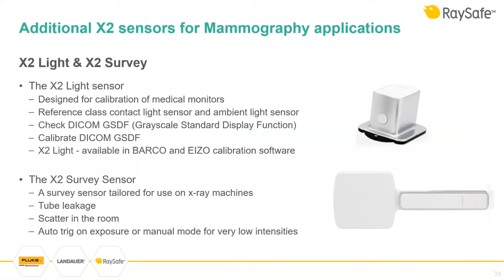Additional X2 sensors for mammography applications: the X2 Light sensor is designed for calibration of medical monitors — it's a reference-class contact light sensor with the capability to measure ambient light. You can use it to check or calibrate the grayscale standard display function, and it is available as a choice in Barco and EIZO calibration software. The X2 Survey sensor can be used for tube leakage and checking scatter in the room, and is a good tool to teach staff working in the mammography room about radiation differences when standing behind the protection screen versus being in the room.